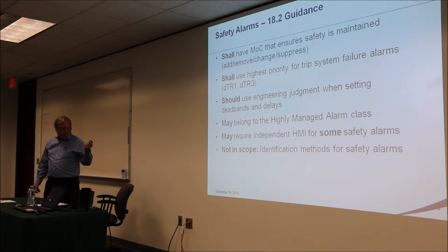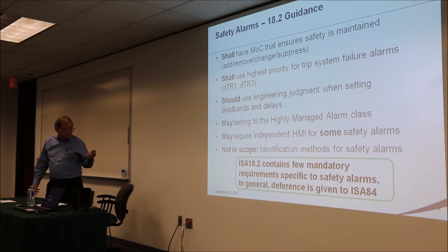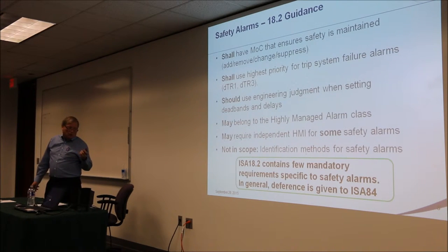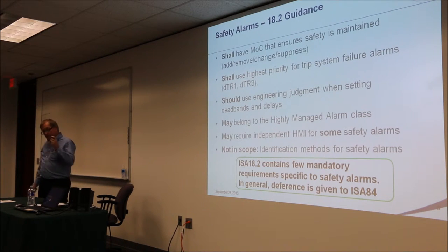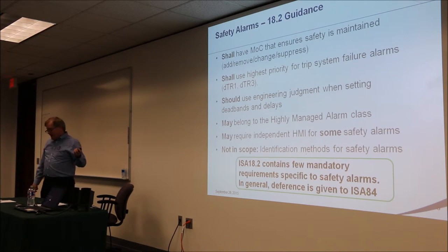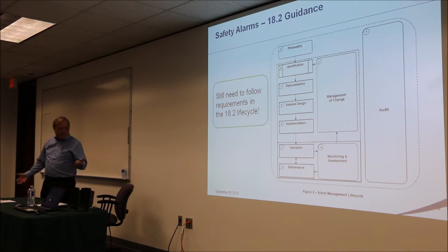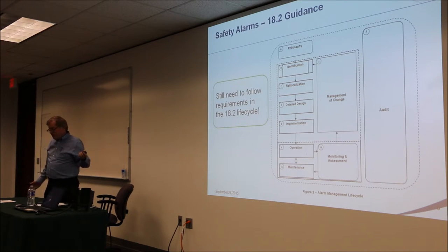The use of the highly managed class is somewhat of a controversial question on the committee. In summary, there are a few requirements in 18.2, but not a whole lot, and there are a number of places where deference is given to ISA 84 — for more detail on safety instrument systems and safety aspects of alarms, the standard says to go to ISA 84. That said, safety alarms, being a subset of all alarms, still have to follow the alarm management life cycle, which carries a lot of requirements.